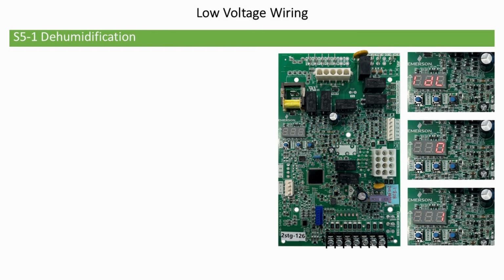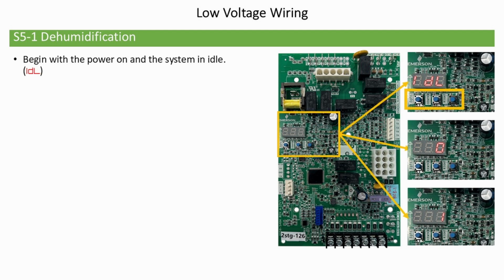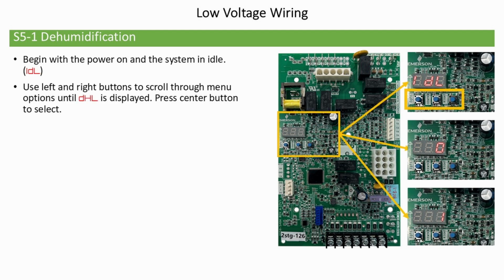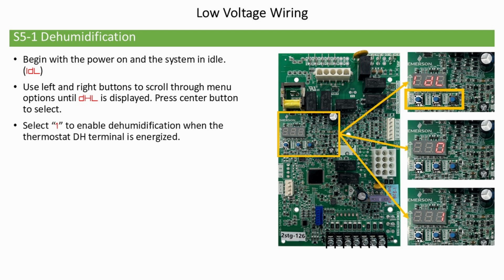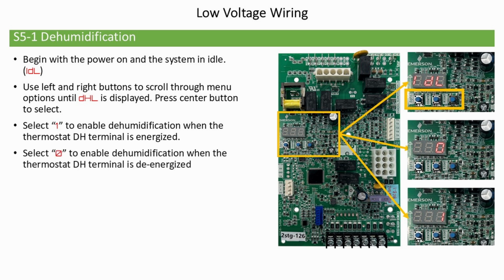S5-1 Dehumidification. Begin with the power on and the system in idle. Use the left and right buttons to scroll through the menu options until DHL is displayed. Select 1 to enable dehumidification when the thermostat DH terminal is energized. Select 0 to enable dehumidification when the thermostat DH terminal is de-energized. Default setting is 1.